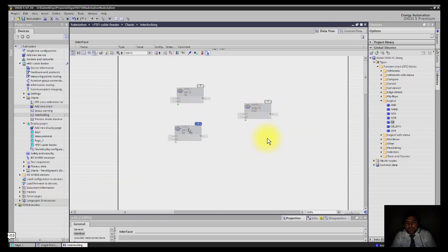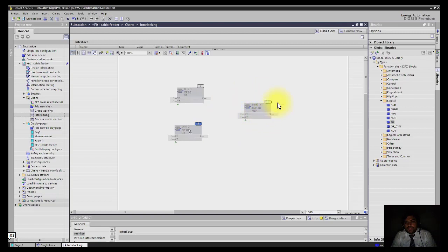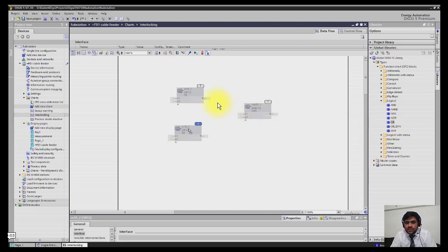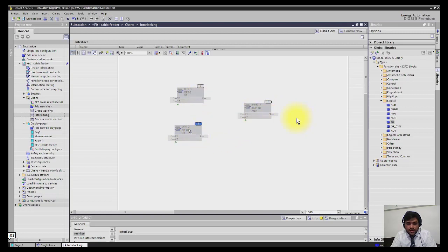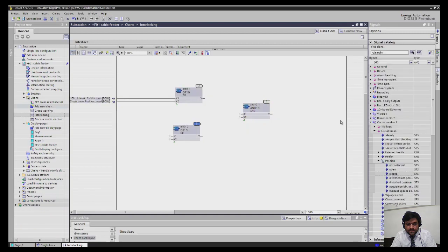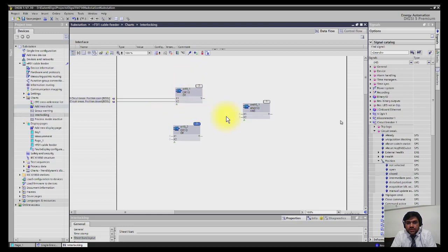Let's draw the logic for the breaker. The breaker can only be operated if the isolator position is valid and the breaker position is valid. First of all, we have to choose an AND gate, one for isolator and one for breaker. If both have valid position, then it should enable the operation of the breaker. I will drag two AND gates here.